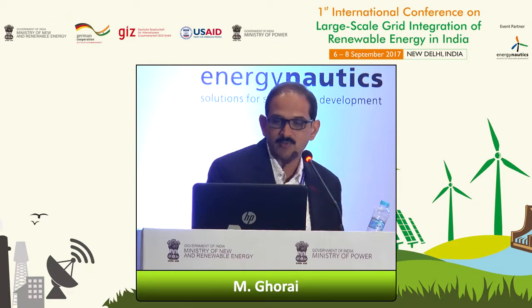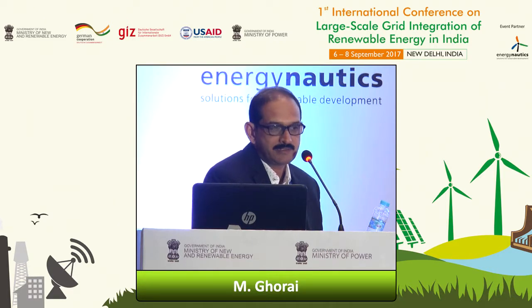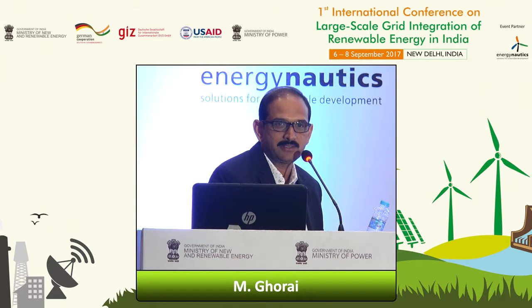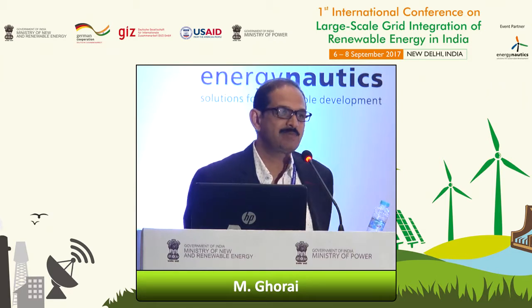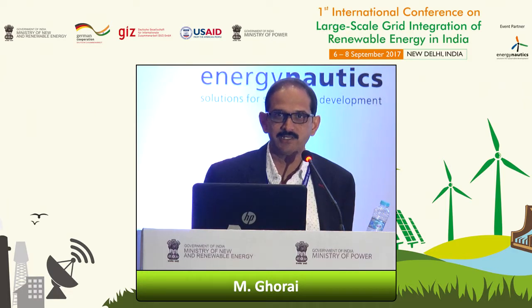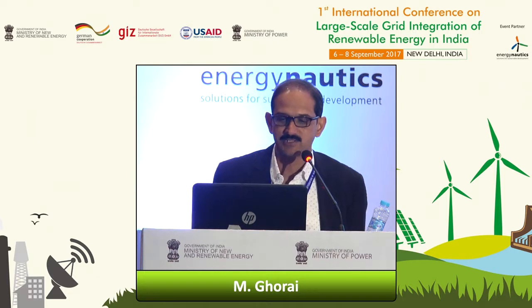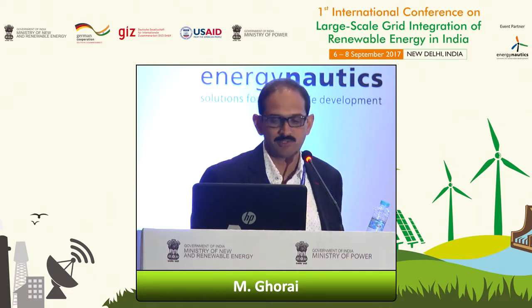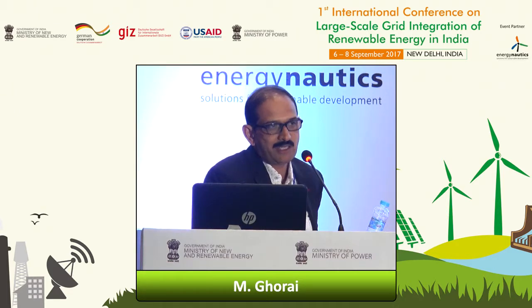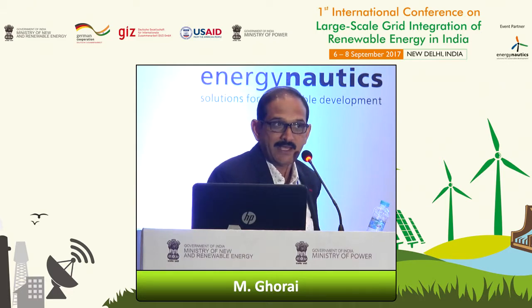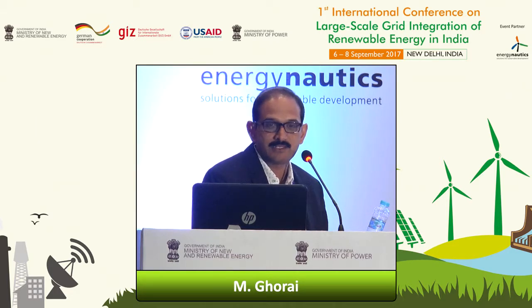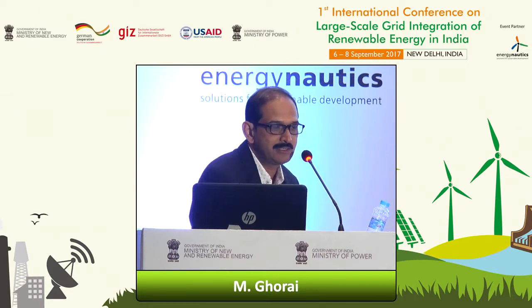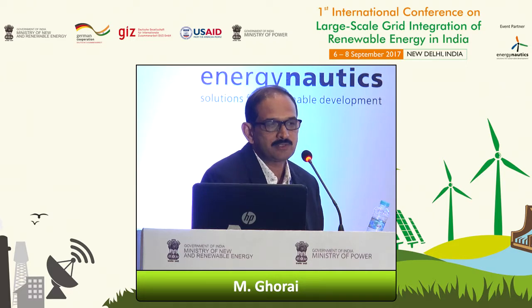If we talk about the India grid code, it has been evolving, and a draft grid code has come out. The LVRT requirement was there in the 2015 grid code, but the new draft version is still being reviewed by the authorities. It has requirements of voltage control with an adjustable loop, and a power factor requirement of plus or minus 0.95, like any other grid code. They have also added a speed of response requirement: it should come back to 95% within 1 second, which is quite fast. This is similar to the UK one.